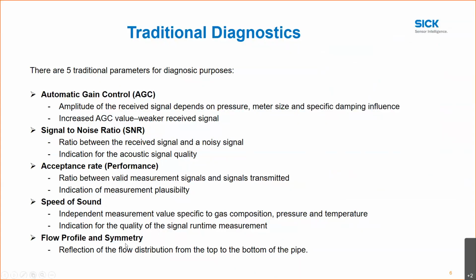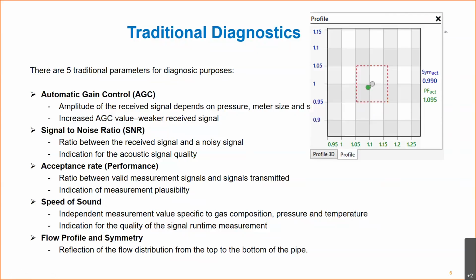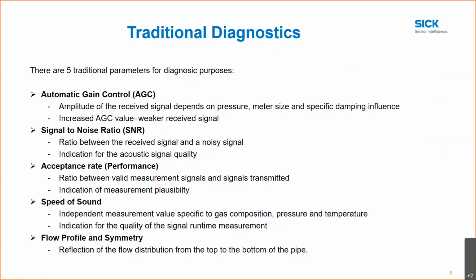And again, flow profile and symmetry is a reflection of the flow distribution from the top to the bottom of the pipe, as we saw in that example earlier. Whenever you have a block flow conditioner, it disturbs the flow coming through the meter, and potentially could cause some inaccuracy in the meter. So as we see here, the diagnostics is a quick way of identifying whether you have a good profile or not. Is my indicator inside the box? If it is, then you probably can be assured that you have a good flow profile and good symmetry in your meter. So all these are some of the traditional diagnostics that still exist in the next generation meter.